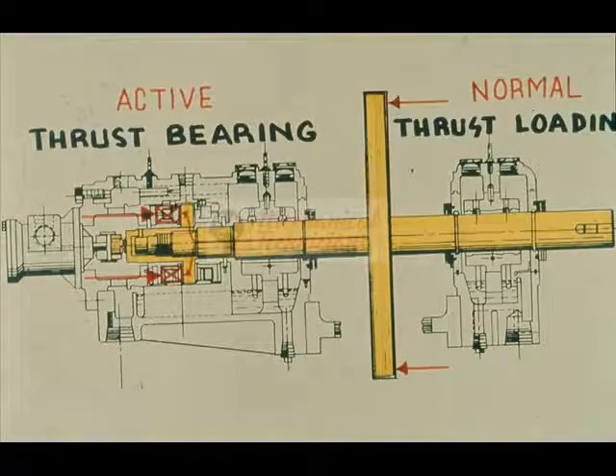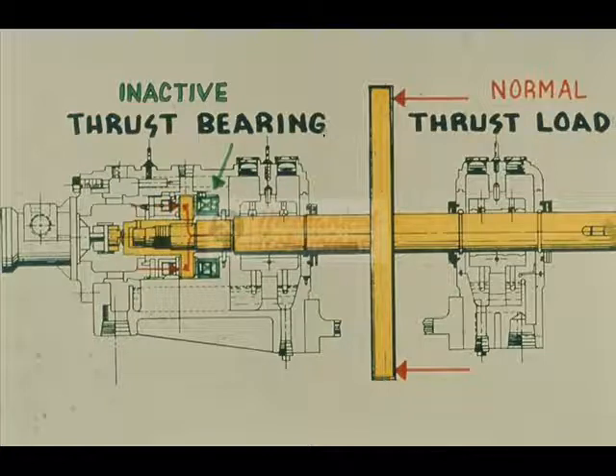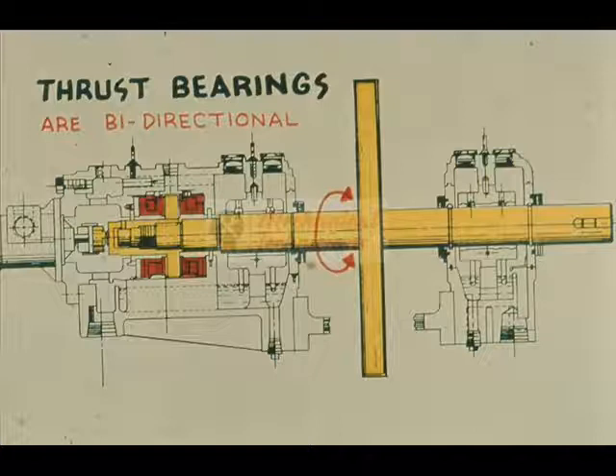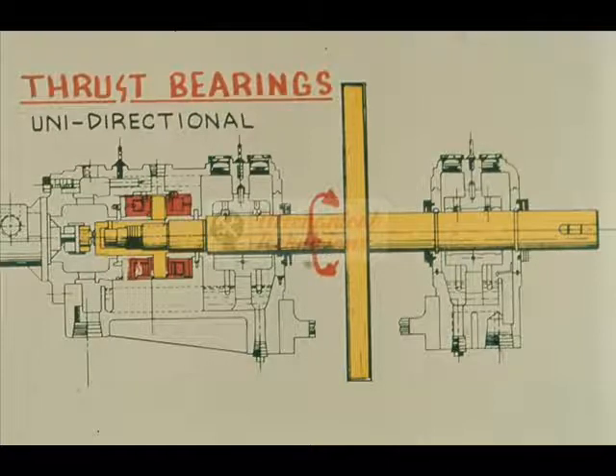The bearing carrying the thrust load during normal operation of the machine is called the active thrust bearing. The bearing unloaded during this period of operation is known as the inactive thrust bearing. Some thrust bearings are designed to run with a thrust collar that may rotate in either a clockwise or counterclockwise direction — these bearings are said to be bi-directional. Other thrust bearings are unidirectional, meaning they are designed to run with a thrust collar that turns in only one direction.